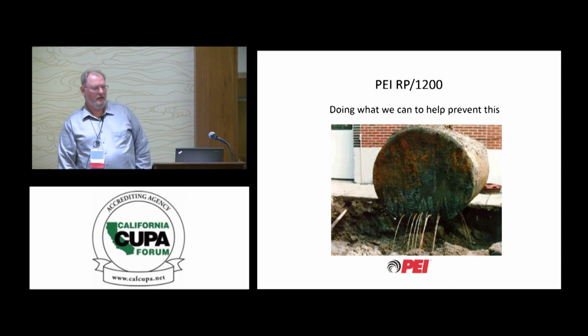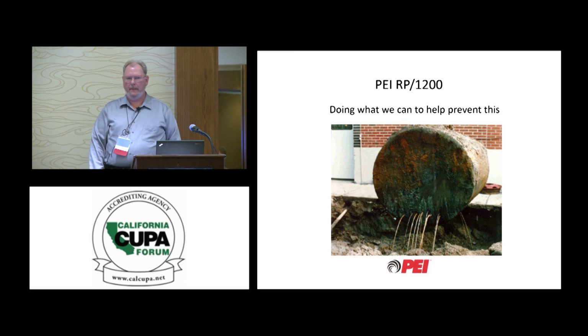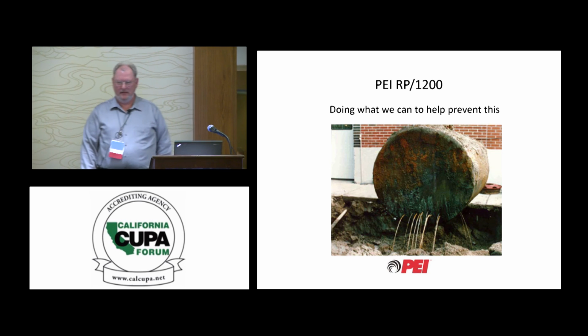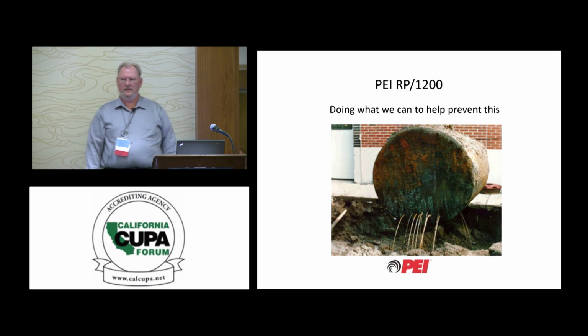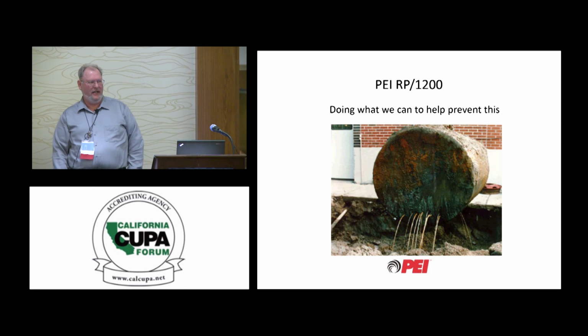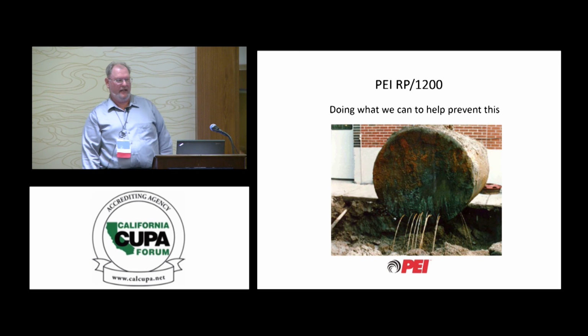Okay, next question. Do the overfill requirements in Title 23 match the overfill requirements in 40 CFR Part 280? Okay, see a hand here. She said no. She's correct. Thank you. I kind of highlighted the differences between 40 CFR and Title 23, and that the addition in Title 23 is that you provide the restriction occurs at 95% of capacity.